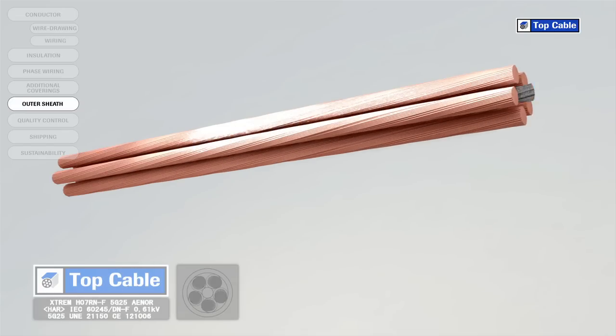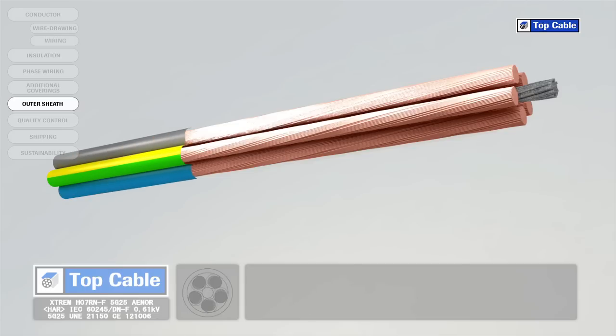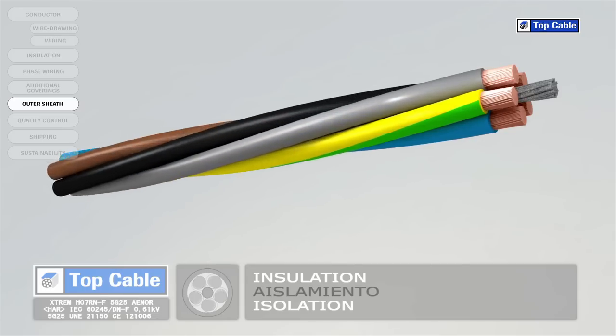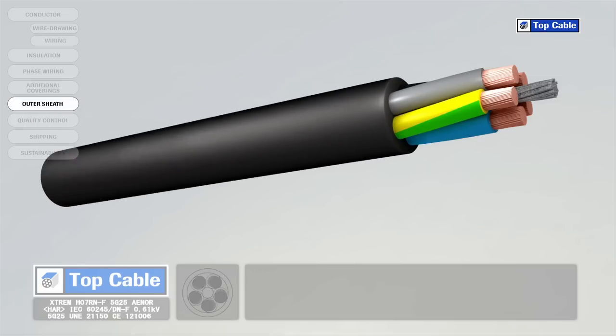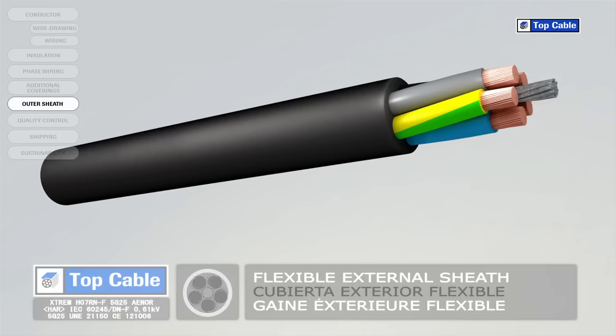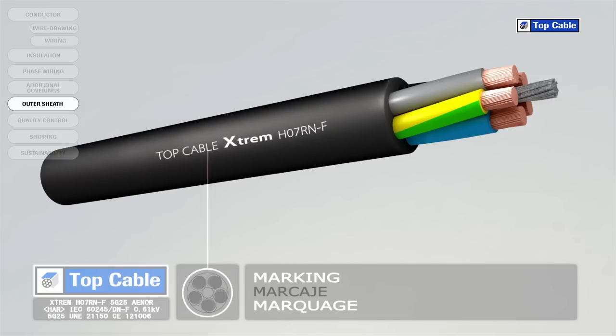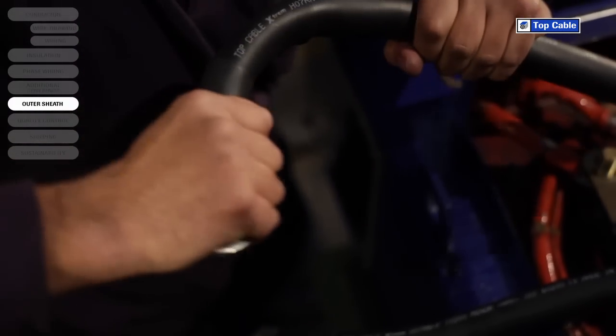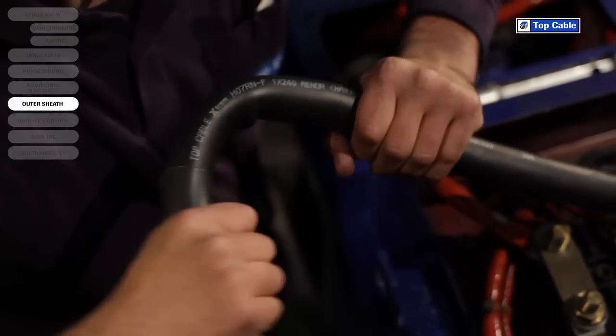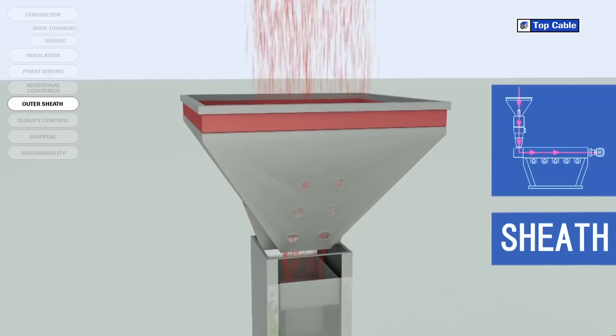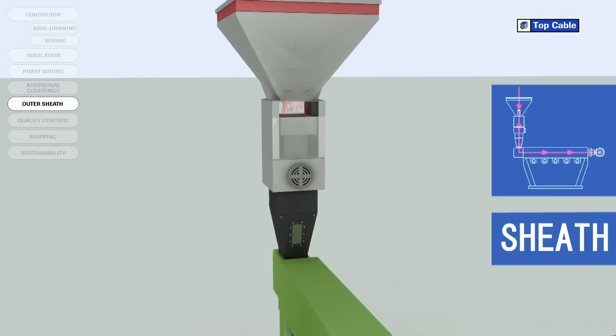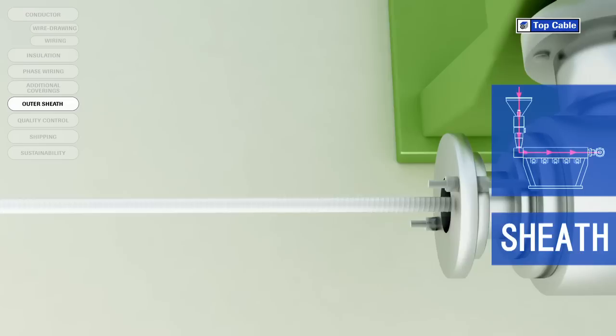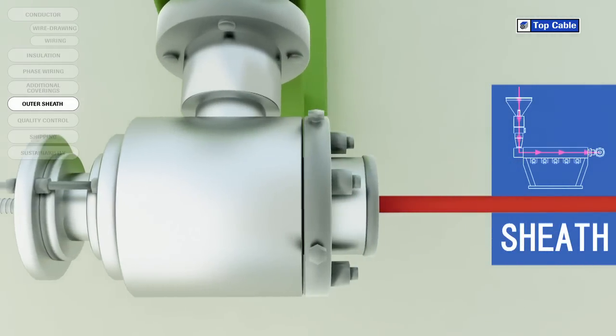Cables usually have an outer polymer covering for protection. This is called the outer sheath. The sheath protects the conductors and their insulation from external elements which may change their electrical properties, such as moisture. It also protects them from mechanical aggression, which may occur during the installation of the cable. As with the insulation, the outer sheath can be made from a thermoplastic or a thermosetting plastic. The outer sheath is applied like the insulation via a process of extrusion at high temperature. The sheath may be made from different materials depending on the required protection level, the final flexibility of the cable, and the work environment.